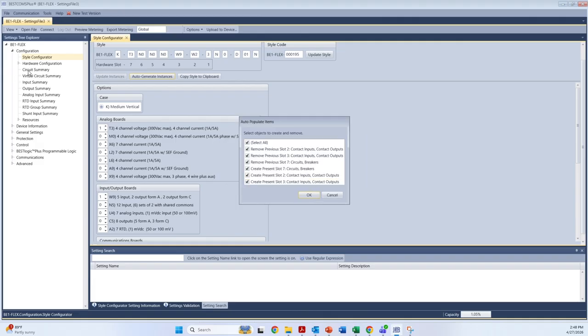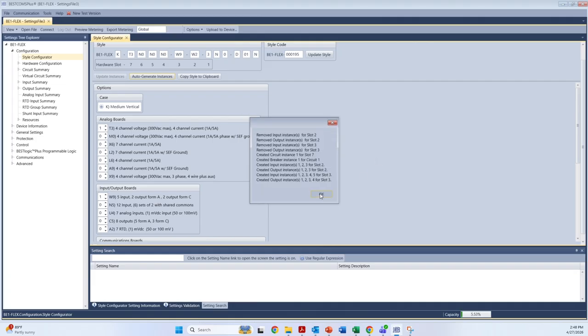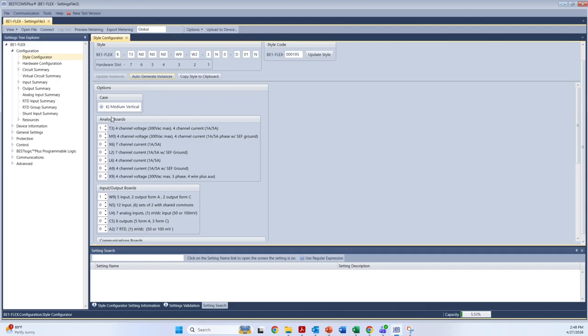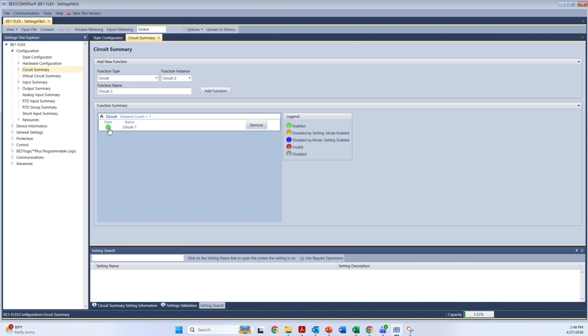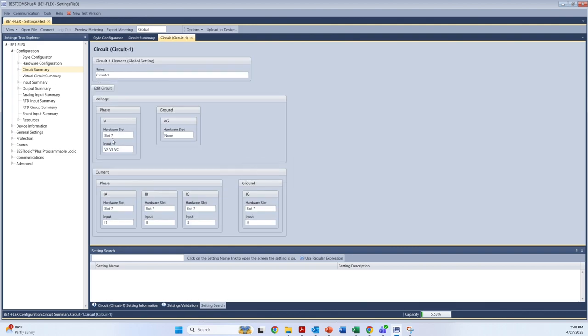And what that does is it maps out circuits, inputs, and outputs based on the hardware and firmware you selected for your particular application. So notice now I have a circuit here. And we will go into the circuit and navigate to the hardware tab, and it shows you that I'm looking at slot 7 VA, B, and C, and the currents IA is slot 7 I1, IB is I2, and IC is I3.